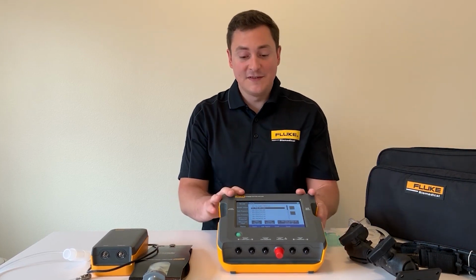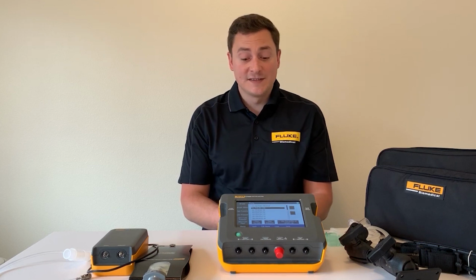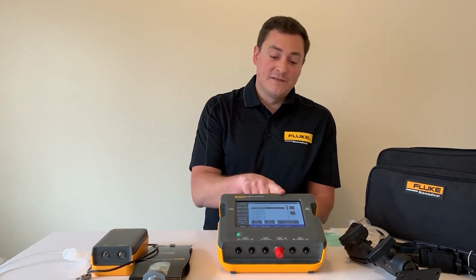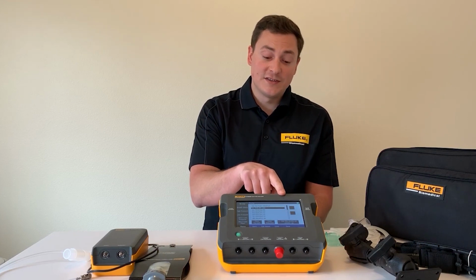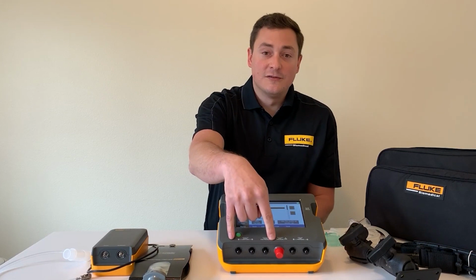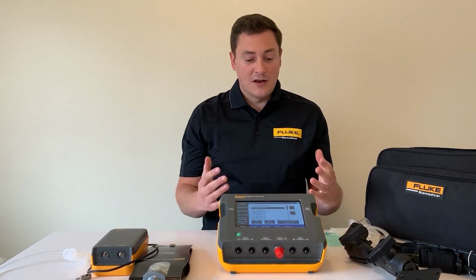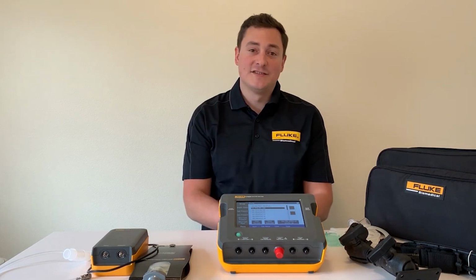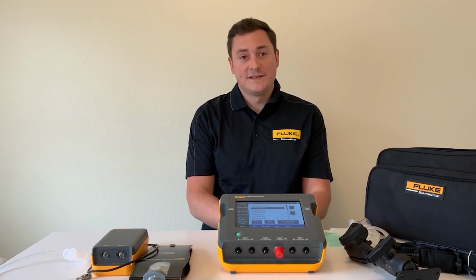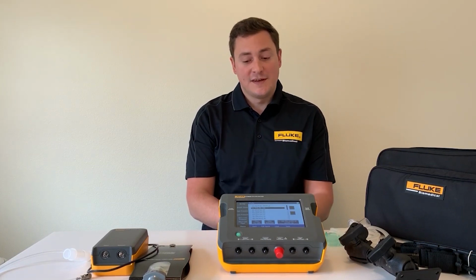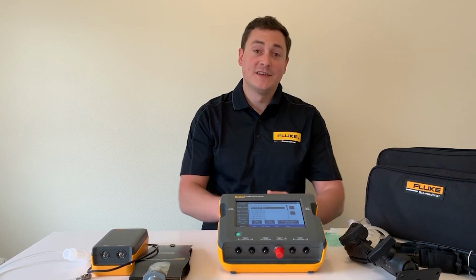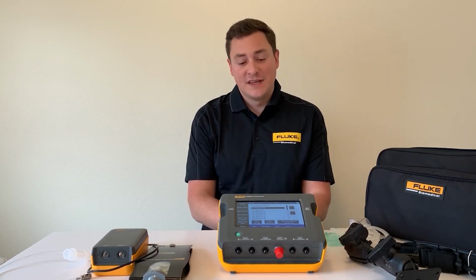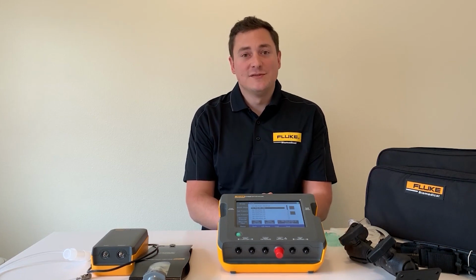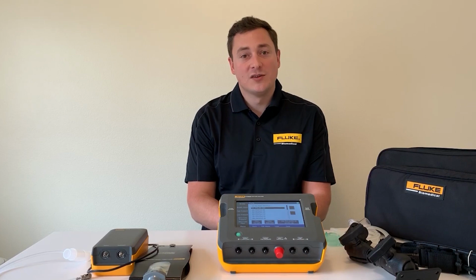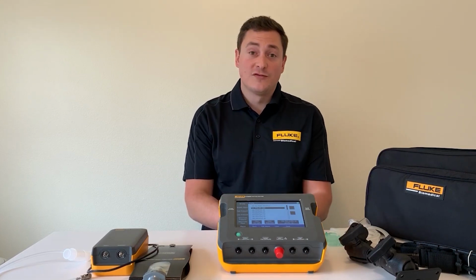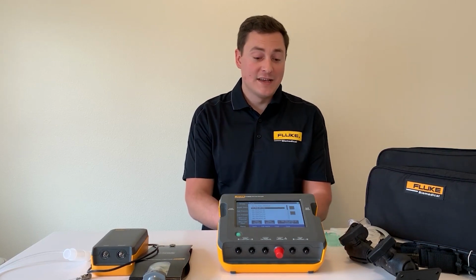So again, this is the VT900A. Some of the differences between that and the VT650 are oxygen saturation accuracy, the availability of the connection to the vapor anesthesia tester, external TTL trigger, and the ultra low flow and ultra low pressure ports here at the front. Other things that are helpful to note is the accuracy of both of those units. That was one of our biggest focus points when we were developing the product. So we used the Fluke Molblock L system to give us those really high accuracy measurements. And the other thing is, for new and used units, you can get an ISO 17025 accredited calibration. So again, if you need more trust in your measurements, that's available from Fluke Biomedical as well.